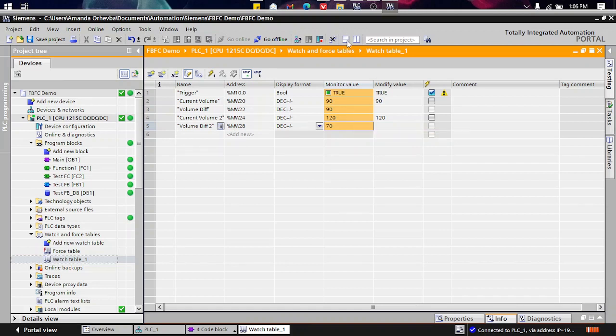It just shows that with a function, you have no dedicated memory, whereas with a function block, you have dedicated memory. So you can use it whenever you need to call things that were done in a previous scan, a previous cycle of that function block.